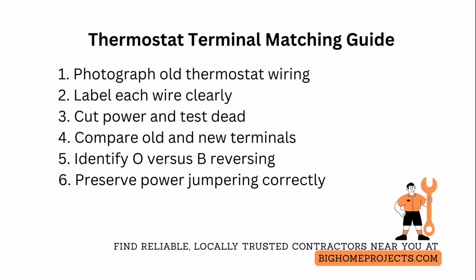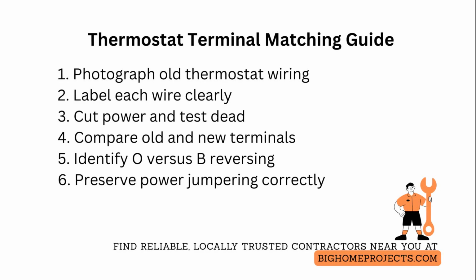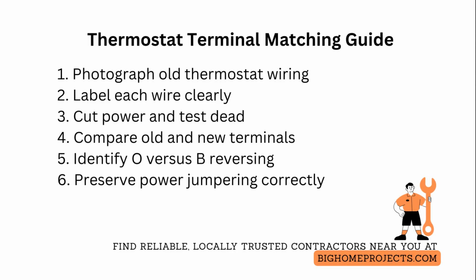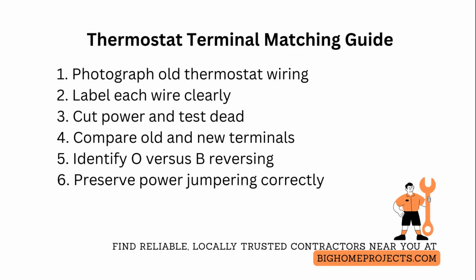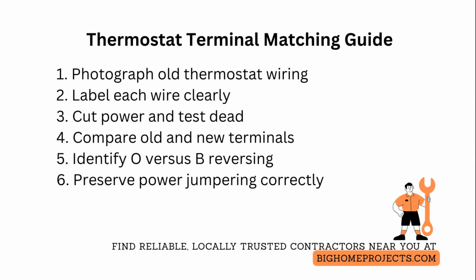Never rely on wire color because installers and previous owners mix colors. Shut power at the furnace or air handler breaker and double-check with a non-contact voltage tester that there is no live voltage on the control board before touching terminals. Even low-voltage systems can cause shorted relays if miswired. Compare the old thermostat label and the new thermostat installation guide side by side. Trace each function: call for heat, call for cool, fan, common, reversing valve.